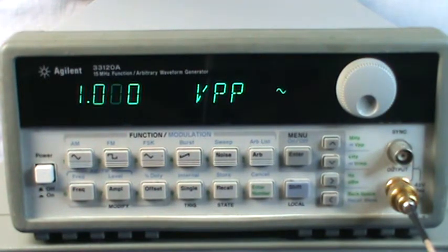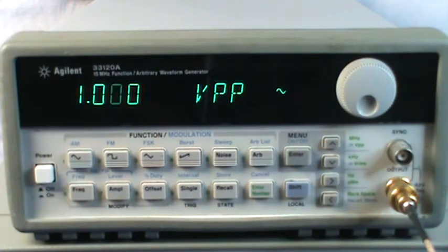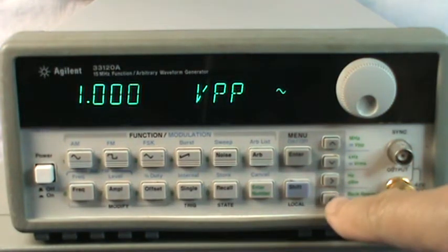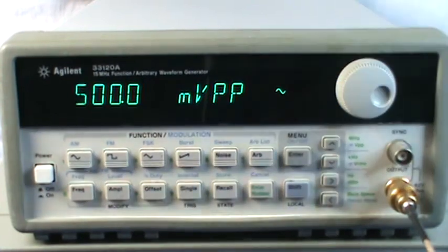So the generator is working in fact like a current generator. As you'll notice, the amplitude now is double, and it's normal because this generator now will provide to the exterior the full voltage of the machine. So basically, if I want to go back to 500 mV, I have simply to select from these arrows the desired digit to be active, and I have to change back to 500 mV.